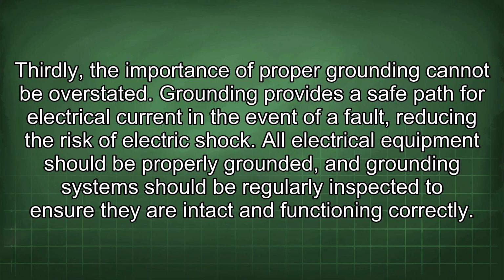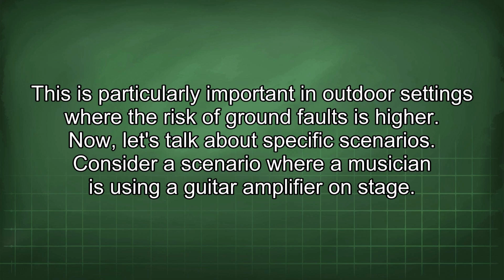Thirdly, the importance of proper grounding cannot be overstated. Grounding provides a safe path for electrical current in the event of a fault, reducing the risk of electric shock. All electrical equipment should be properly grounded, and grounding systems should be regularly inspected to ensure they are intact and functioning correctly. This is particularly important in outdoor settings where the risk of ground faults is higher.